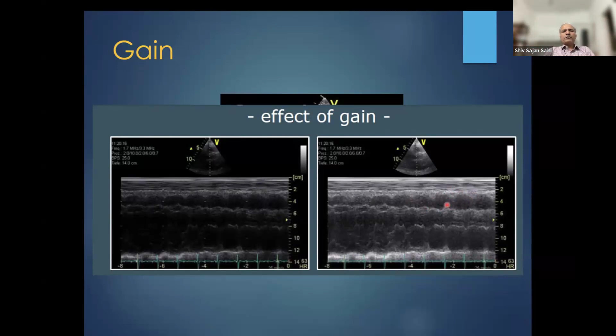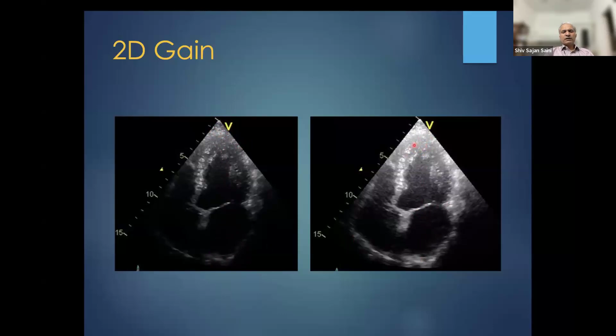So what is the way out? The way out is, and this is another depiction of this 2D gain. When we increase the gain, it improves the signal in equal proportion from the nearby tissues. If it increases the 50% energy from this area, it increases similarly 50% from these two areas. Whereas these two areas are appearing much better, this area, nearby areas, they are appearing much more snowy.